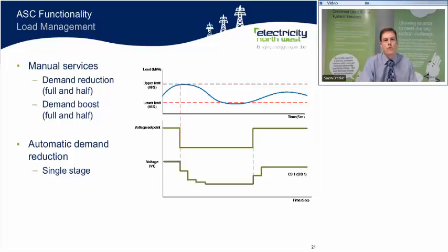There is also an automatic function, which is a single stage of voltage reduction, so that if you look on the graph here, as the load reaches a set point, or a trigger point, a voltage reduction is applied, and then you can see the effect of transformers tapping down over time, which would have the effect of delivering a voltage reduction. We can see the voltage reduction in the top trace. And after that, sustained for a period, the voltage reduction can be removed again.